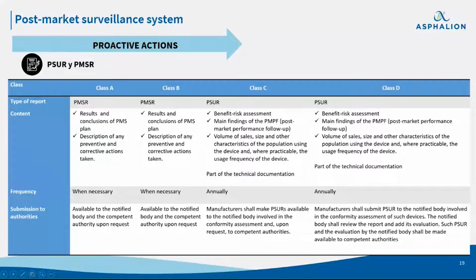To finish with the proactive actions, we have the safety reports. We have two types, PMS reports and PSURs. Their elaboration depends on the IVD class established. As you can see in this slide, for class A and class B, we have to prepare post-marketing surveillance reports. The content of these reports is the results and conclusions of the PMS plan and also the description of any preventive and corrective actions taken. We have to prepare this type of report when necessary, and they must be available to the notified body and the competent authorities upon request. In the case of Class C and Class D, what we have to prepare are PSURs. In these PSURs, we have to include a benefit risk assessment and also the main findings of the post-marketing performance follow-up.